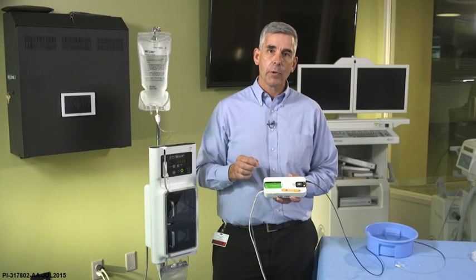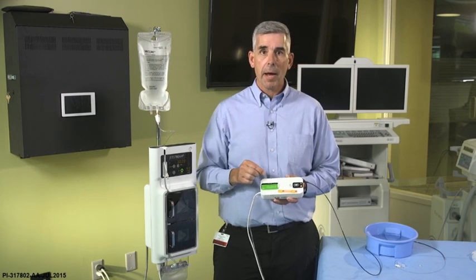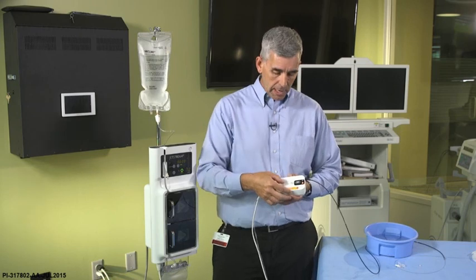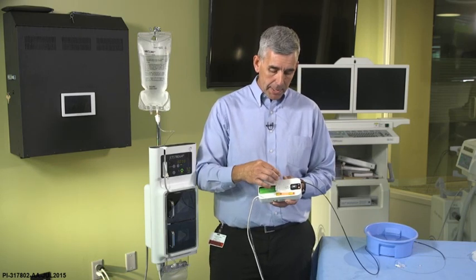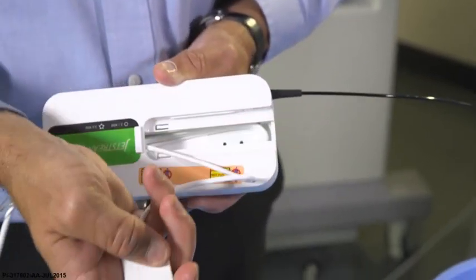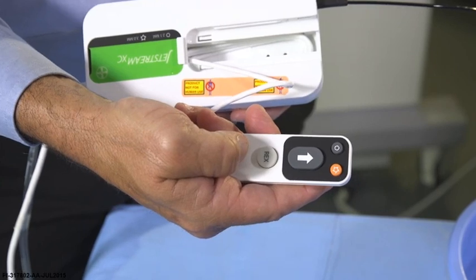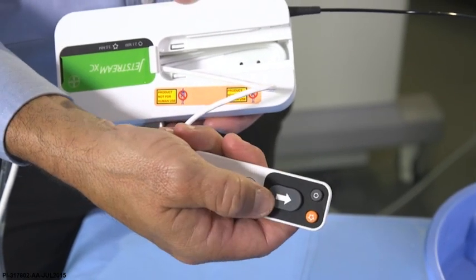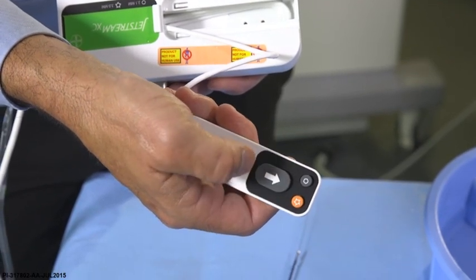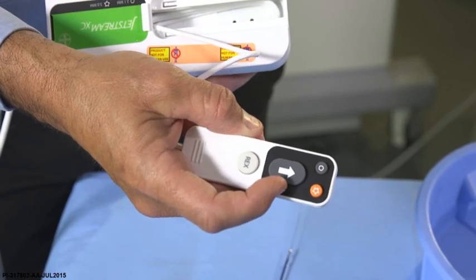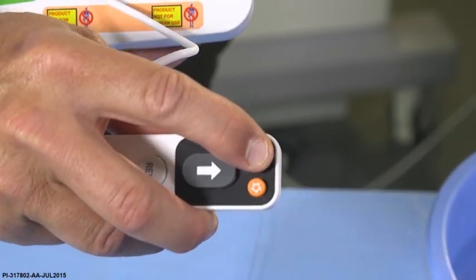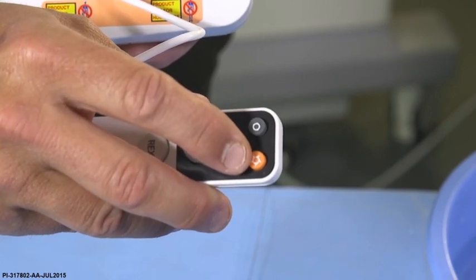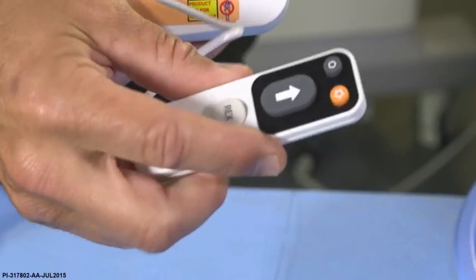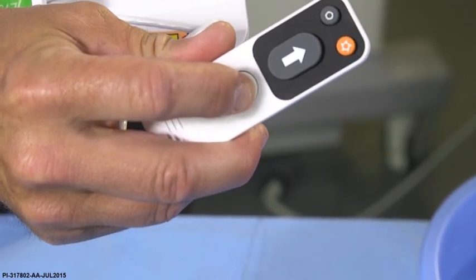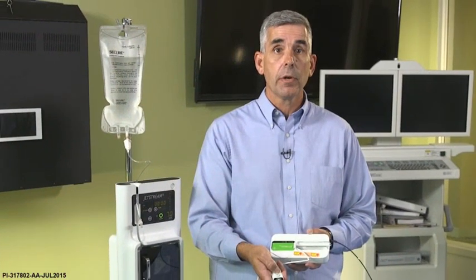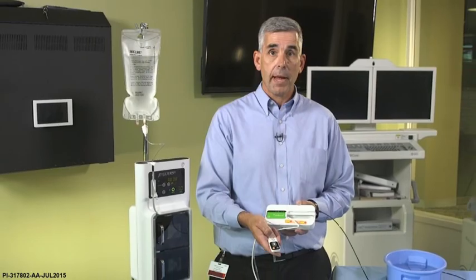With the Jetstream now backloaded over the wire and advanced to the treatment site, let's review the pod and the operational buttons. These buttons are on the controller, which are tethered into the pod. They can be used either in the pod, or you can remove the activation buttons and use the controller through the tether. First, let's talk about the activation button. The large button with the up arrow on it is our activation. This will engage the cutting and aspiration modes of the catheter. You will see two buttons on the top of the controller. The gray button, which will activate in blades down mode, and the orange button, which will engage the blades up activation mode. The Rex button, located behind the activation button, is used for retraction and activates aspiration when withdrawing the catheter in preparation for the next pass or removing it from the body.